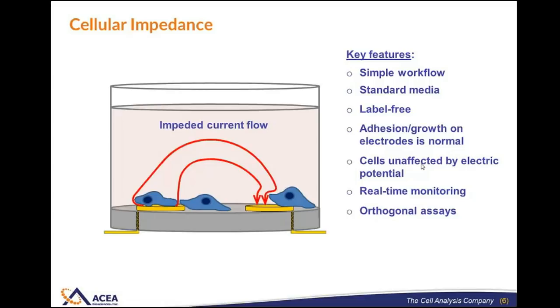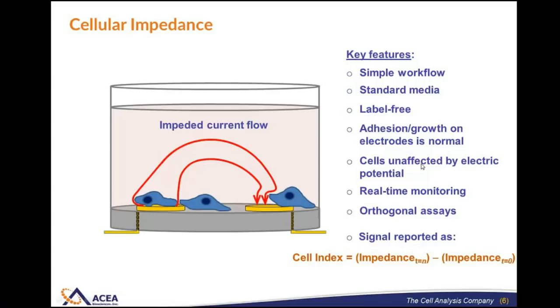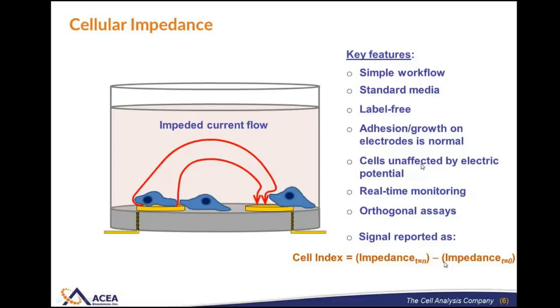The signal that the xCELLigence system reports is a parameter we call cell index. This is simply the impedance signal — the resistance to this flow of electric current at whatever time point you're interested in — subtracting out the background impedance measured prior to adding cells. There are actually a large number of electrodes presented in an interdigitated array, where one electrode is in black and the other in blue. This approach allows us to cover about 75 percent of the well bottom, enabling us to monitor many thousands of cells simultaneously, resulting in exquisite sensitivity.